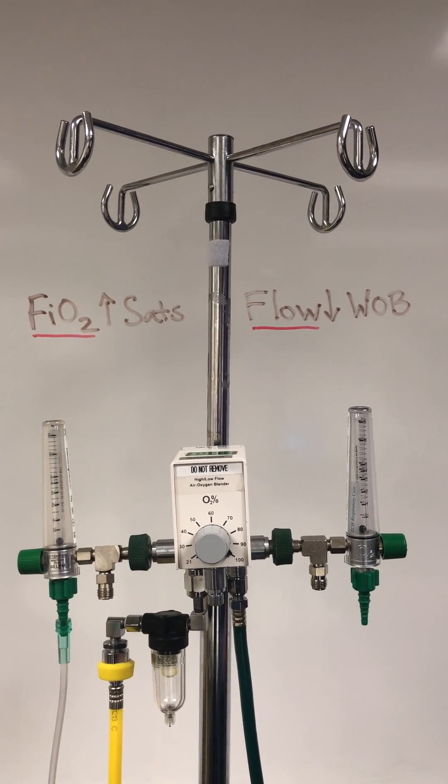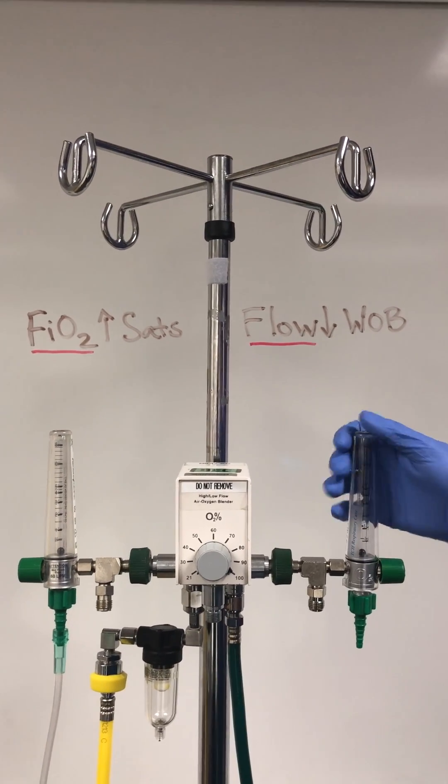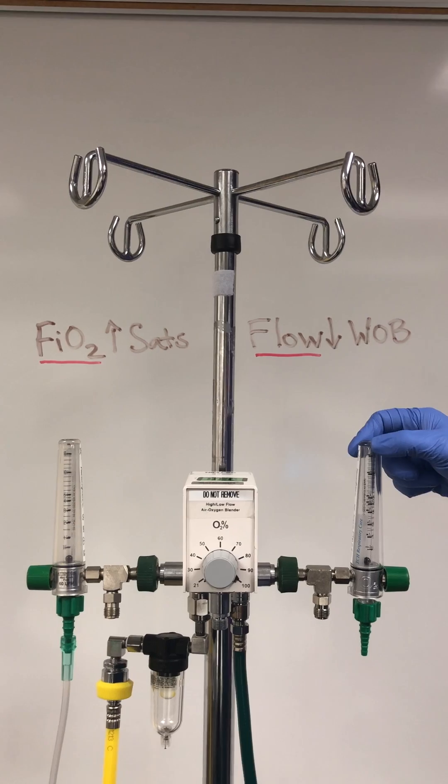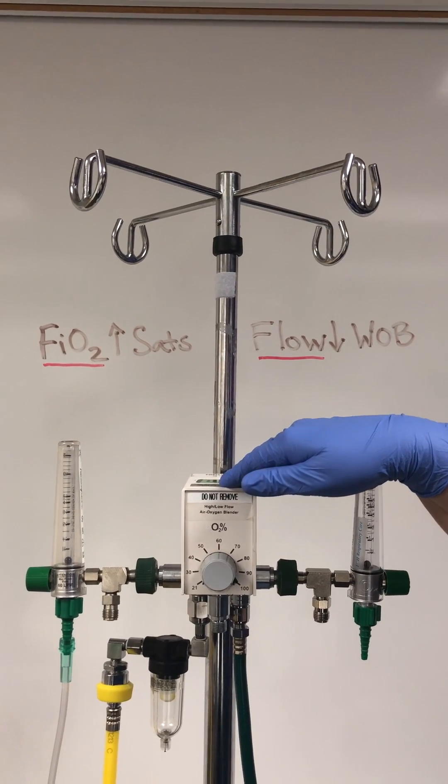High flow nasal cannula. There are two components to the high flow nasal cannula. There's a flow meter on the side, it goes from 0 to 15, and then the blender goes from 21 to 100% oxygen.